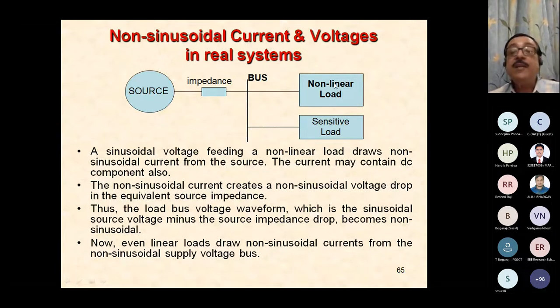Now, if I have a nonlinear load here, it is drawing a non-sinusoidal current right through. So that voltage drop in the impedance is going to be non-sinusoidal. So a sine wave minus a non-sinusoidal waveform is going to be a non-sinusoidal waveform, or rather a distorted sine wave. So the bus voltage here becomes a distorted sine wave now, and everybody else connected to the bus starts seeing a distorted sine wave. So this is how the bus voltages are distorted because of nonlinear loads. This nonlinear load can be any power electronic equipment that is connected here.